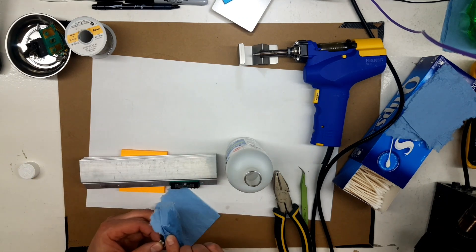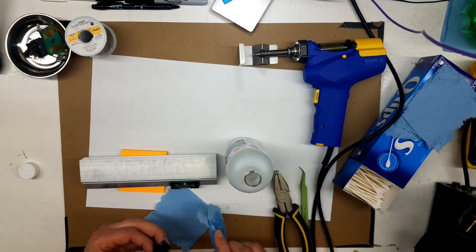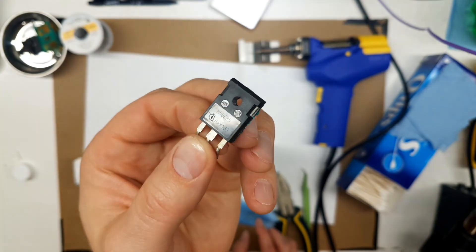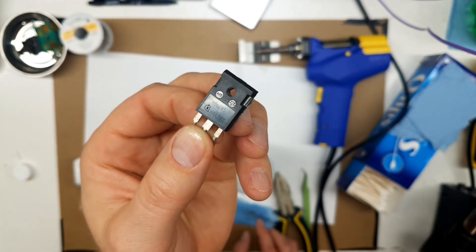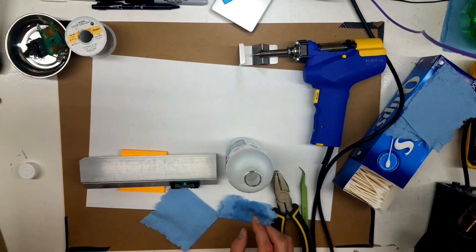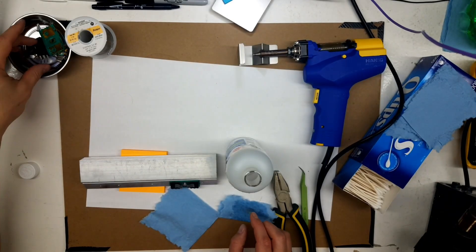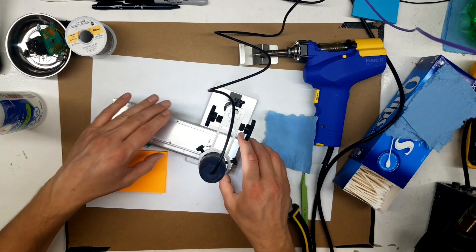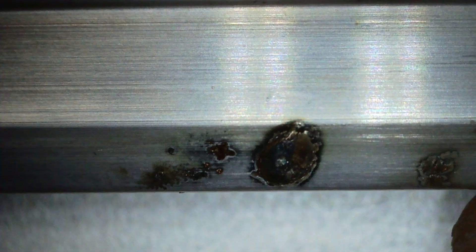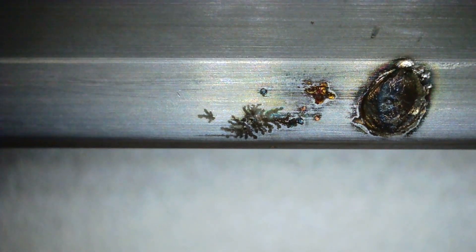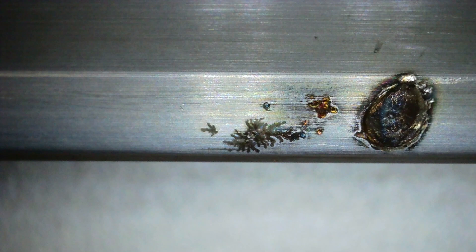So we need to figure out what IGBTs these are. I don't know if you can see that clearly or not. We'll get the microscope out. Yeah, look at all that arcing. And if you feel that with your finger, it's right in there. There's trenches. Nice little bit of fractal burning there.